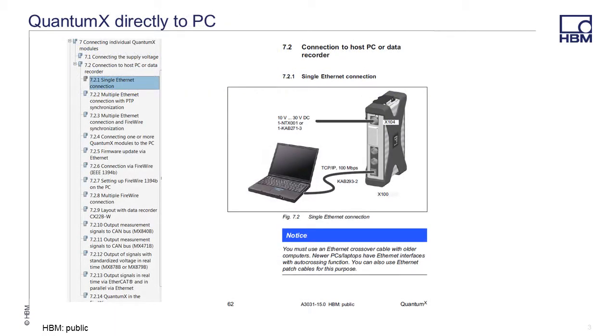The QuantumX Operating Manual, Chapter 7, covers the different topologies for connecting QuantumX modules. The first topology we will cover is a single QuantumX module directly connected to a PC via Ethernet. The image here shows this connection — a standard Ethernet cable connecting the PC to a QuantumX module.